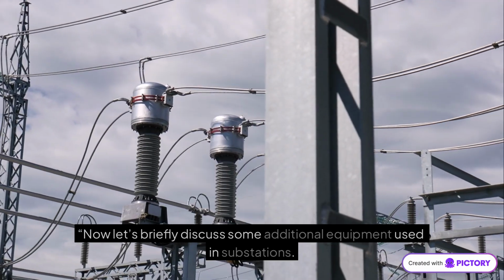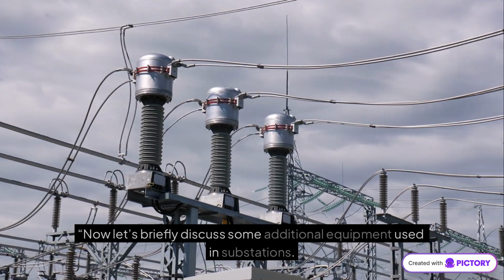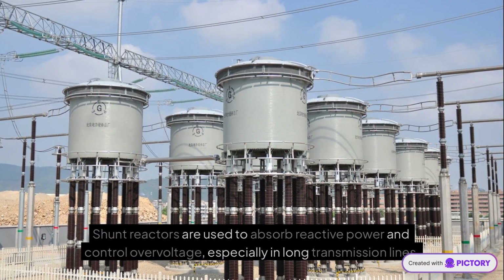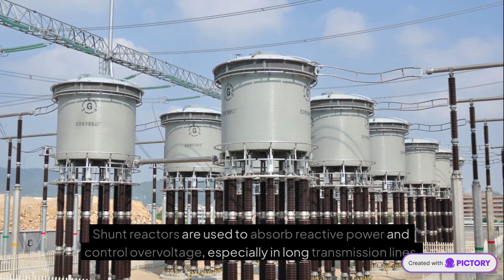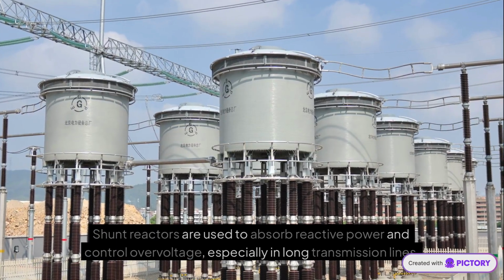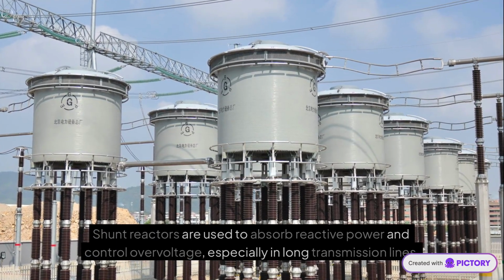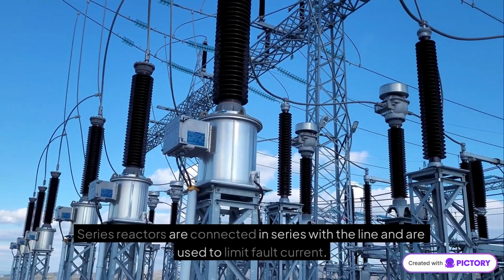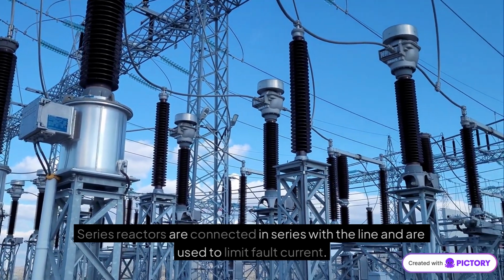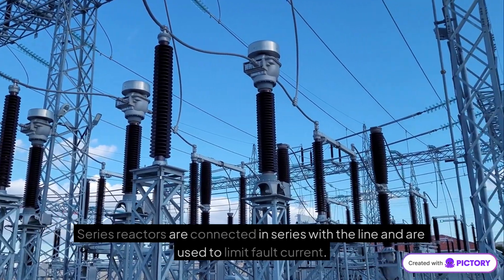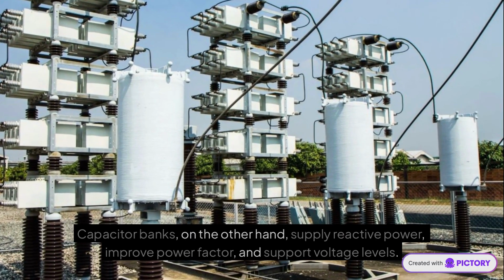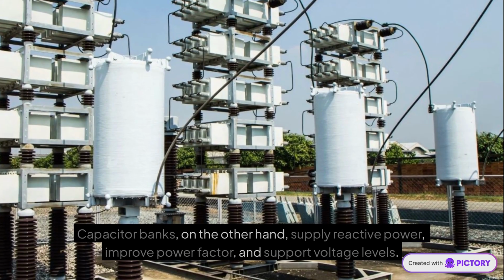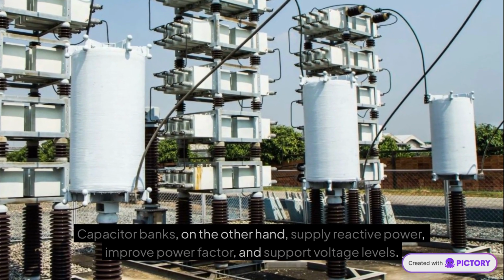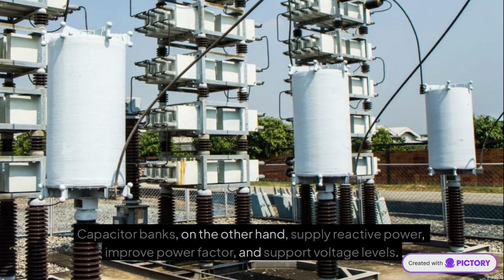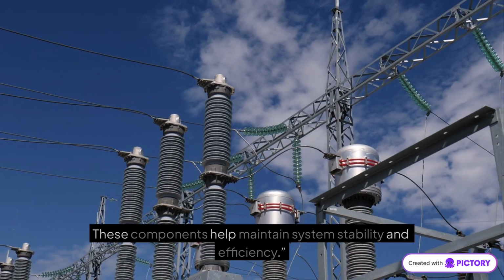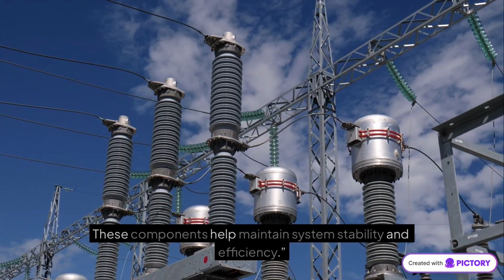Now let's briefly discuss some additional equipment used in substations. Shunt reactors are used to absorb reactive power and control overvoltage, especially in long transmission lines. Series reactors are connected in series with the line and are used to limit fault current. Capacitor banks, on the other hand, supply reactive power, improve power factor, and support voltage levels. These components help maintain system stability and efficiency.